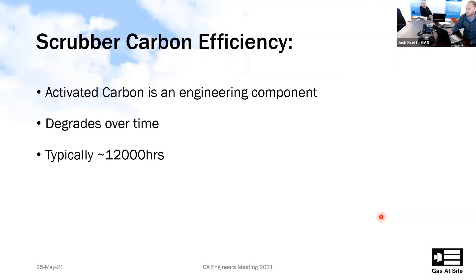So how do we test? How do we measure to see where your carbon efficiency is at on your scrubber? We connect an analyzer to the outlet of the scrubber to measure the atmosphere going back to the room, and we get a performance profile that you can see in this green curve. In this example, we've got our room at 1% carbon dioxide, as shown by this blue line, and we're measuring what's going back to the room. So you can see here, this is a good performance curve on one cycle, on one drum of the scrubber.